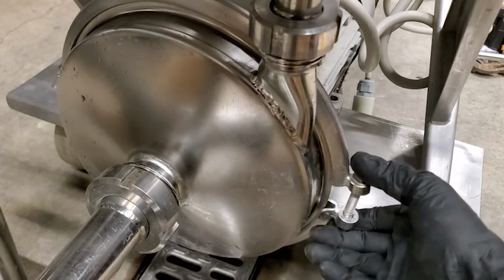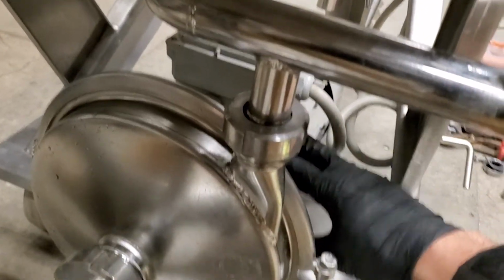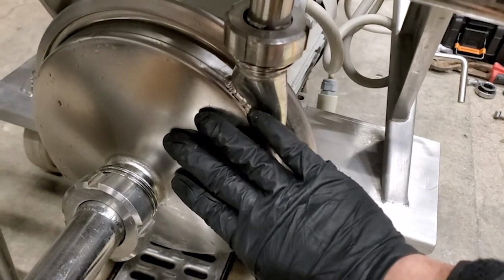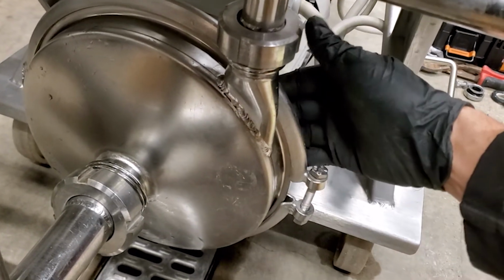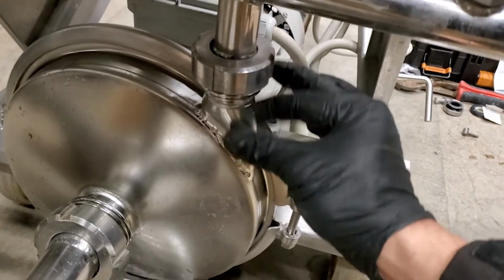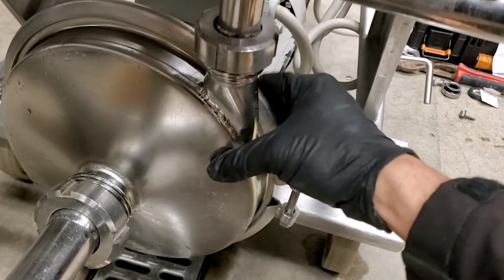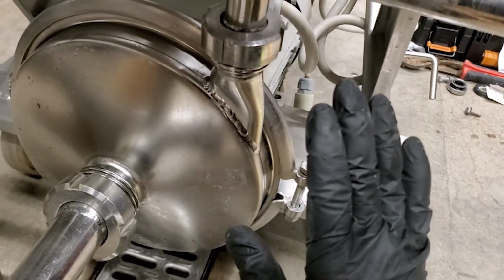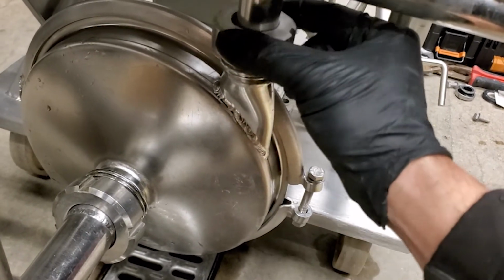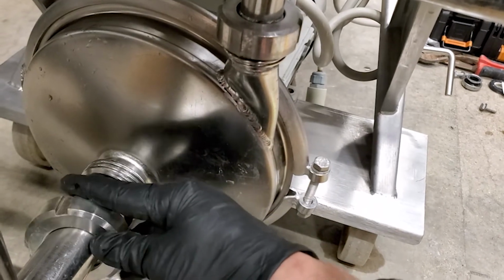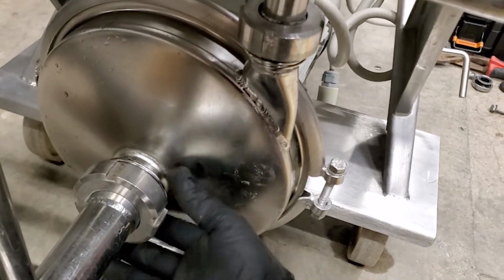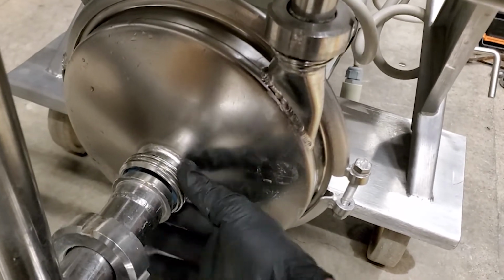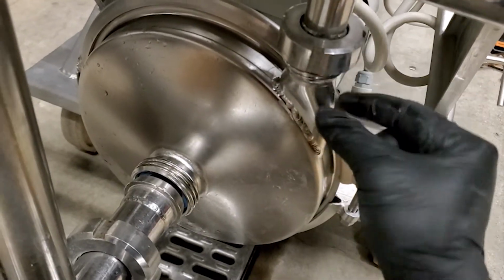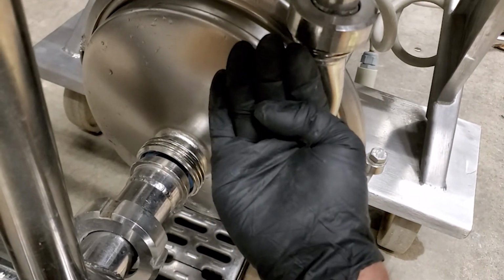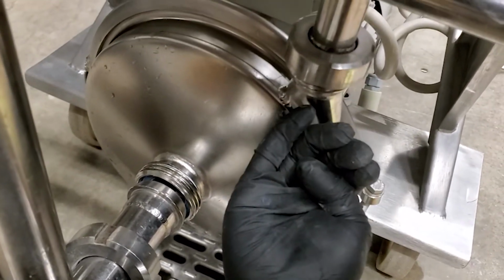The reason I'll leave this somewhat loose for the moment is because you might need to rotate the motor in relation to this pump head, since that back plate is fixed to the motor. If the front plate of the housing isn't oriented vertically, or at least this output isn't oriented vertically to connect here, you won't be able to reinstall the whole thing. This portion is easy, it's always right in the center, doesn't matter where you spin this thing. But sometimes this other part is tilted off a little, depending on how you've installed it.